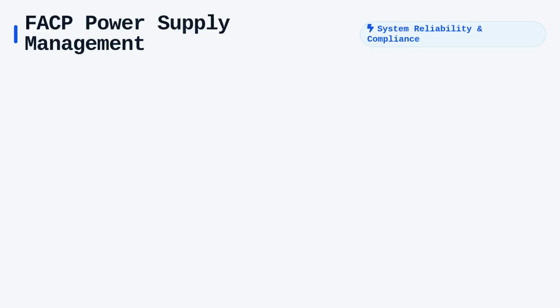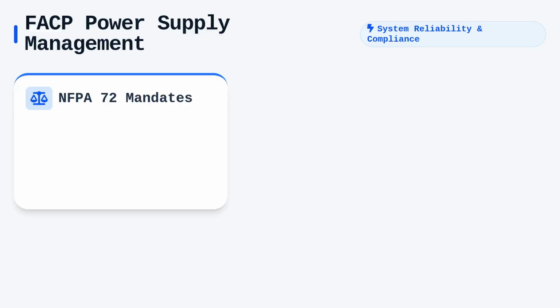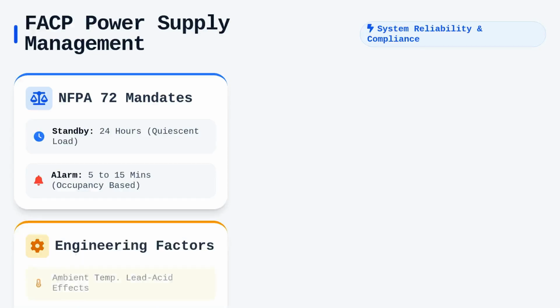Power supply management remains a cornerstone of FAP reliability, as the system must remain functional during primary power failures. NFPA 72 mandates specific battery capacity requirements, requiring the system to operate under its quiescent load for a set duration, often 24 hours, followed by a full alarm load for a minimum of 5 to 15 minutes depending on the occupancy type. Engineers must account for battery derating factors, which include the ambient temperature effects on lead-acid chemistry and the aging process that gradually reduces the total amp-hour capacity of the backup supply.